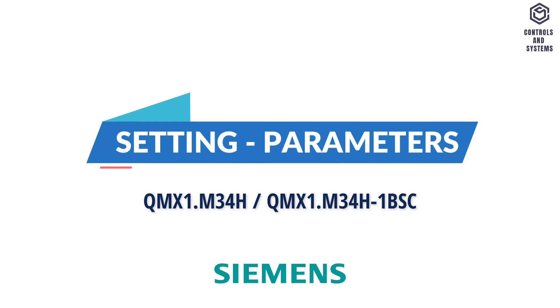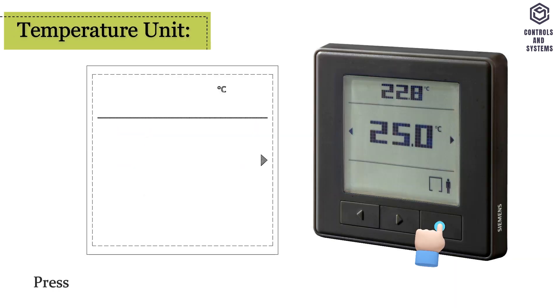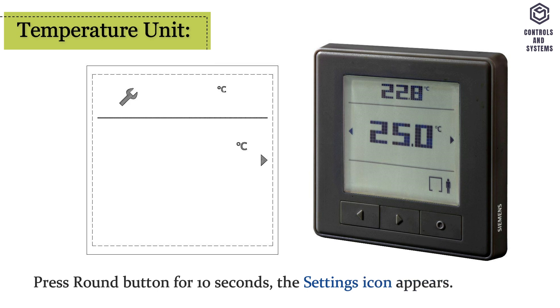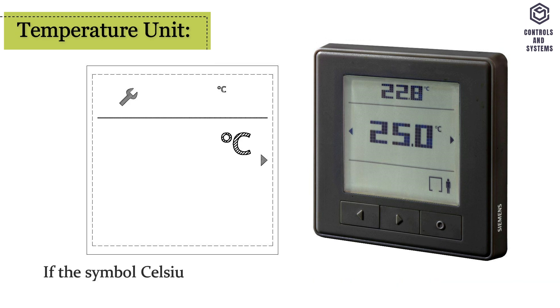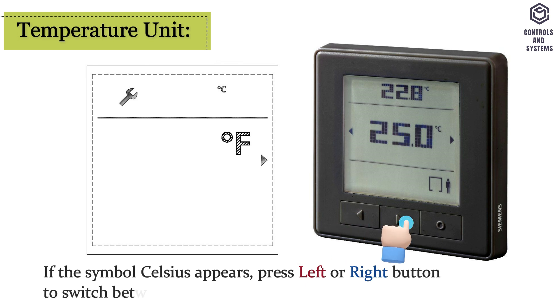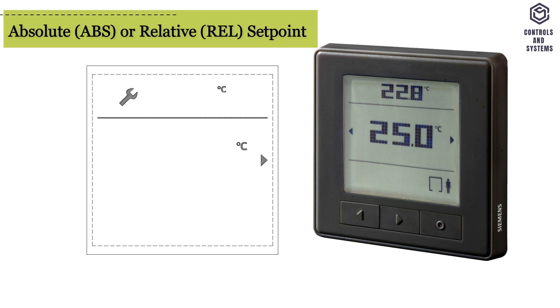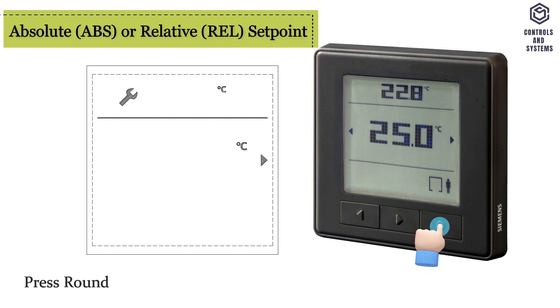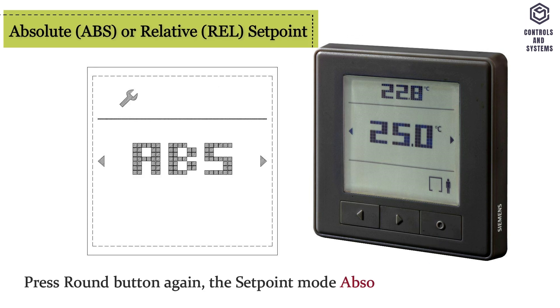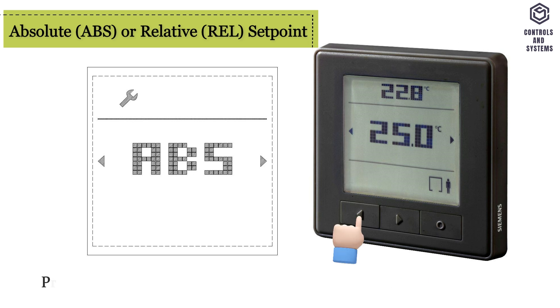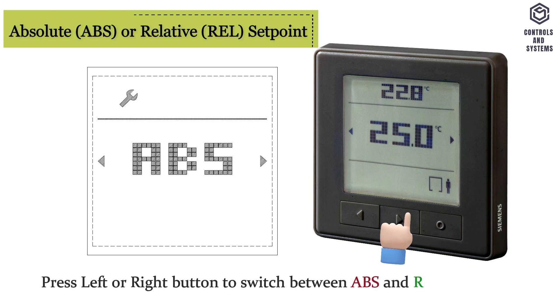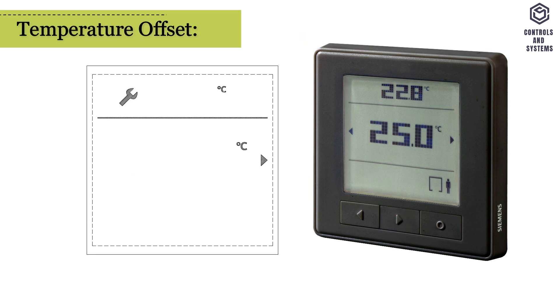Setting parameters — Temperature unit: press the round button for 10 seconds, the settings icon appears. If the symbol Celsius appears, press the left button or right button to switch between Celsius and Fahrenheit. Absolute or relative set point: press the round button again, the set point mode absolute appears; press left button or right button to switch between absolute and relative.